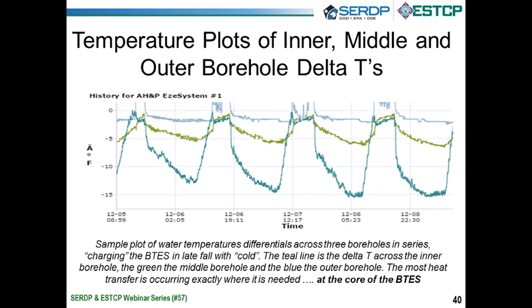All right, so was I telling the truth that we did the cold in the middle where we cared, and then less and less for the outer boreholes? Well, it turns out physics does actually work, and heat transfer is universal. And the teal line there, the deep dips you see, that is with us having instruments on a representative submain of three boreholes. As you can see, left scale is degrees Fahrenheit. We're taking somewhere between maybe a 12 degree and a 15 degree delta T across the inner borehole. So in this case, we're sending it really cold water in the winter, and sure enough, our borehole is taking the hit, taking the 15 degree rise. We're warming up the water 15 degrees, or we're chilling the formation, if you will.